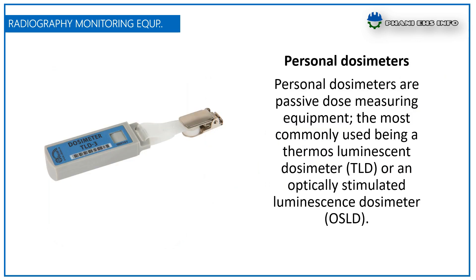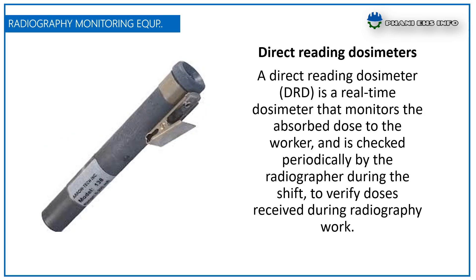Personal dosimeters are passive dosimeter equipment. The most commonly used are the thermoluminescent dosimeter (TLD) or the optically stimulated luminescence dosimeter (OSLD). The direct reading dosimeter (DRD) is a real-time dosimeter that monitors the absorbed dose to the worker and is checked periodically by the radiographer during the shift to verify the dose received during radiography work.